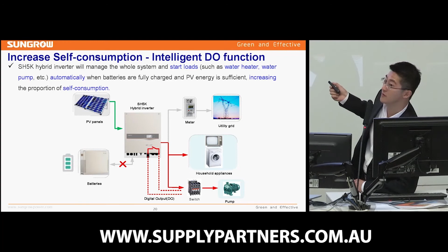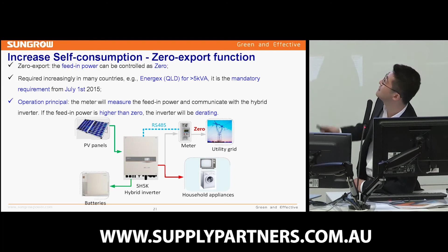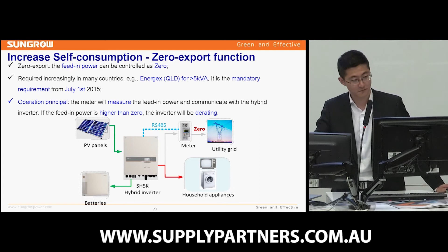The second function is the zero export function, which means the feed-in power can be controlled as 0. Some grid companies require the solar system to use a zero export function. The operating principle is that the energy meter will measure the feed-in power and communicate with the hybrid inverter. If the feed-in power is higher than 0, the inverter will be derating. The whole solar system will produce power to match the load. Basically, the setting is quite simple. There is a selection for feed power. If you set the feed-in power to 0, the zero export function will be activated for the system.